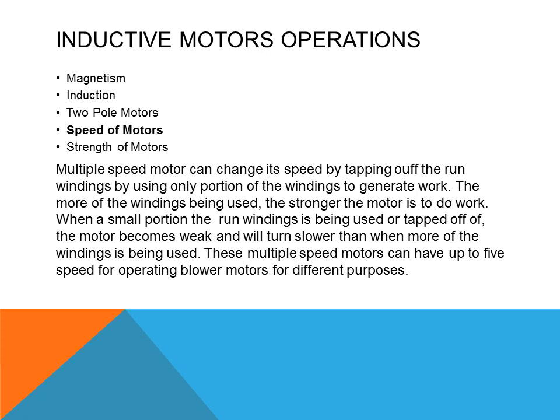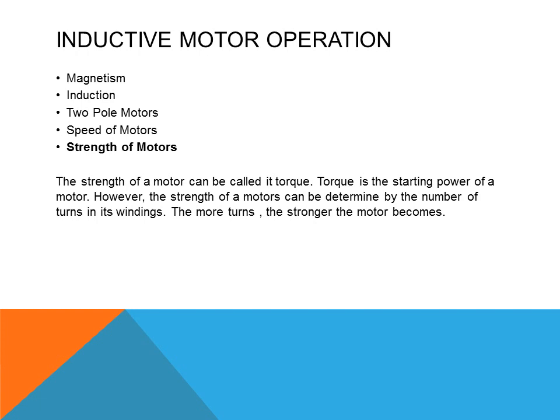Multiple speed motors can have up to five speeds for operating blower motors for different purposes. Most residential furnaces will use a split phase motor that is also a multiple speed motor, with speeds to control different volumes of air for air conditioning and heating. The strength of the motor can be called its torque — the starting power of a motor. The strength of a motor is determined by the number of turns in its windings; the more turns, the stronger the motor becomes.